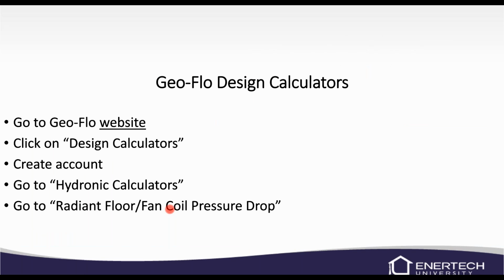We do have some design calculators to help you out with pipe sizing and hydronic calculators for your radiant floor and fan coil pressure drops, and it's geoflo.com. You can sign up just like you do for Enertech, and then you can access a lot of their calculators. They have loop field sizing, pump sizing, quite a few calculators on their website, and they're real good about not sending you junk email. So definitely check it out. We work really closely with Geo-Flo. As a matter of fact, my boss, Jeff Hammond, came from Geo-Flo. So I'm not trying to push their product or anything like that, but I can tell you that their calculators are really nice. So I would recommend using them.